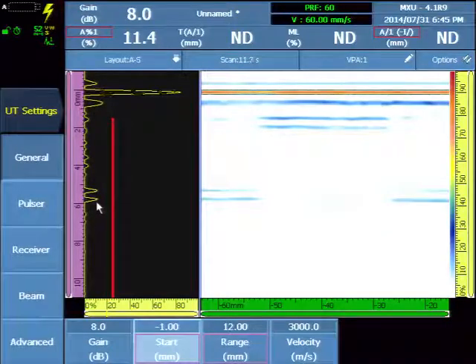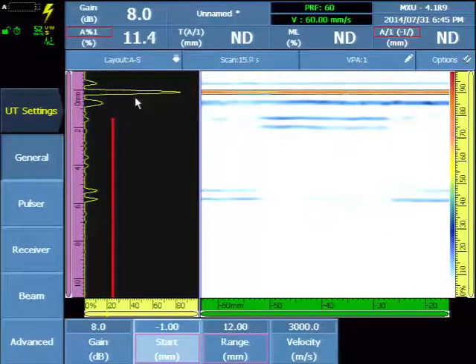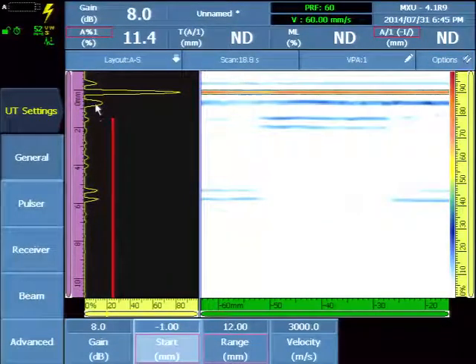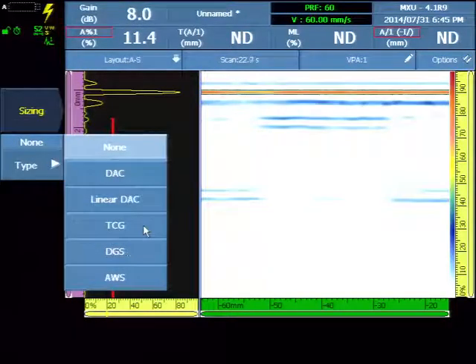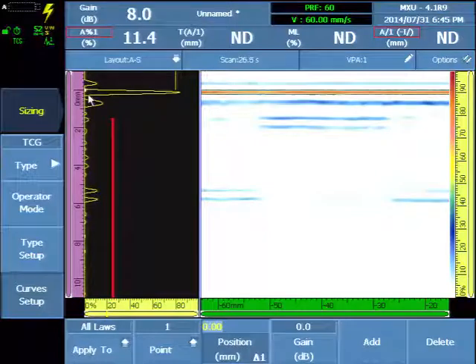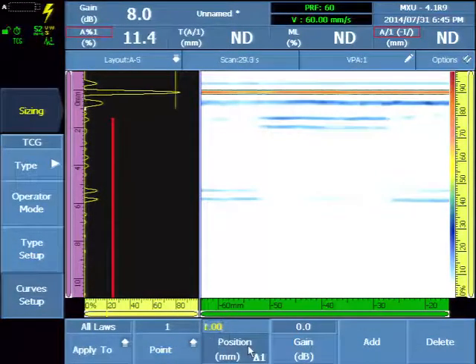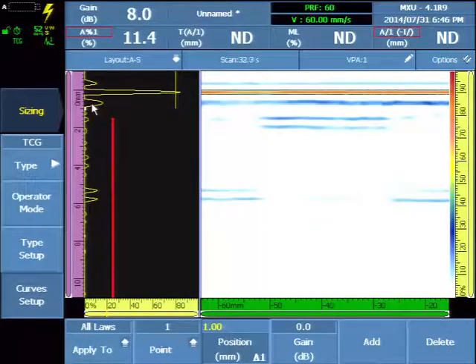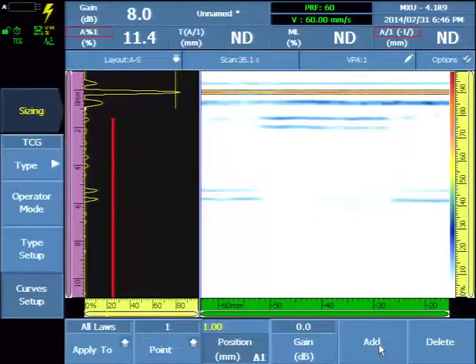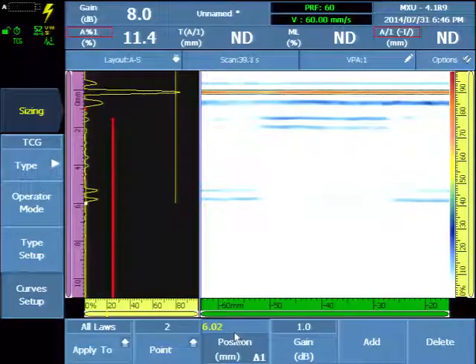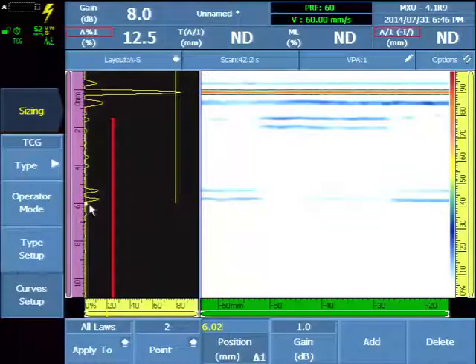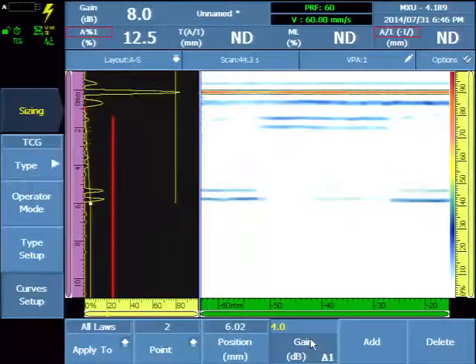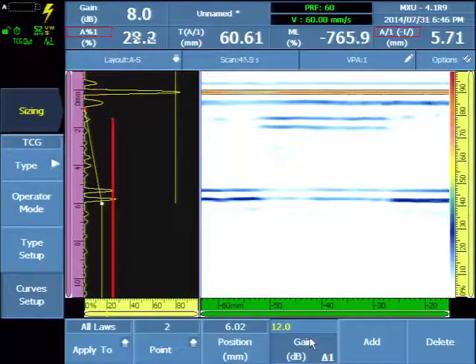We want to increase the amplitude of the back wall without increasing the amplitude of the interface signal because that will hurt our surface resolution. So we'll do that by creating a manual TCG. The first point of the TCG is always present and visible at zero and we're going to move that just off the interface signal so when we raise the gain it won't interfere with our interface. Select add point and move the point to the position of the back wall and increase the gain until the back wall is approximately 75% to 100% amplitude.